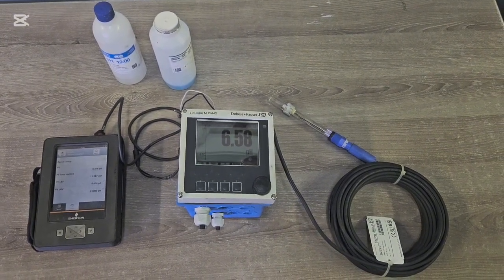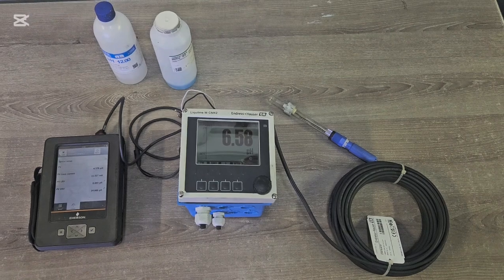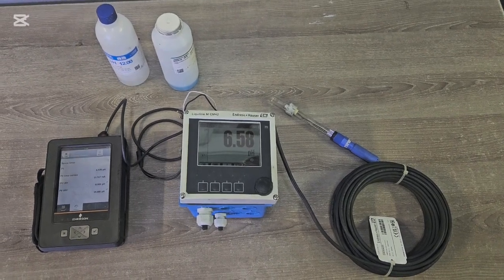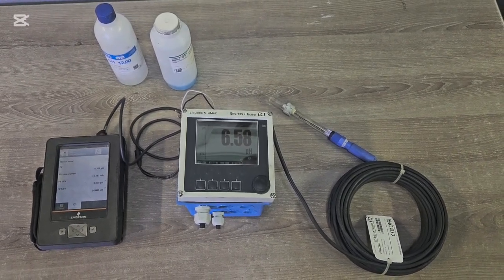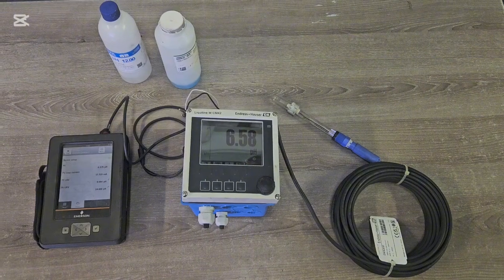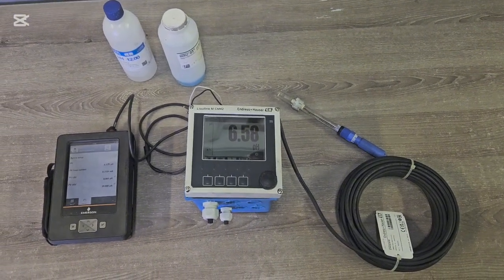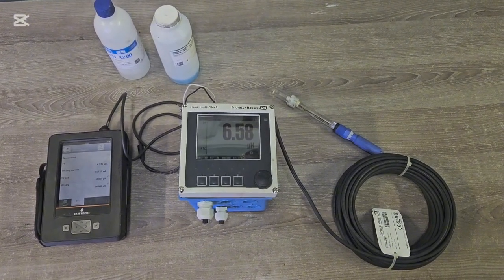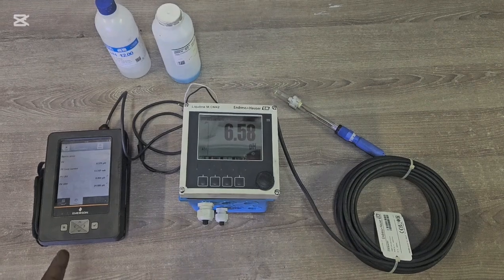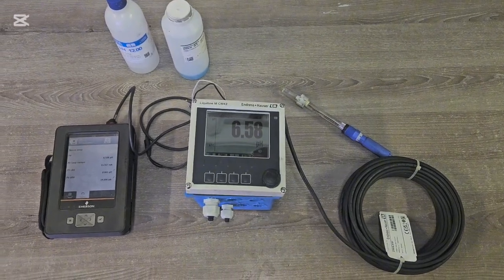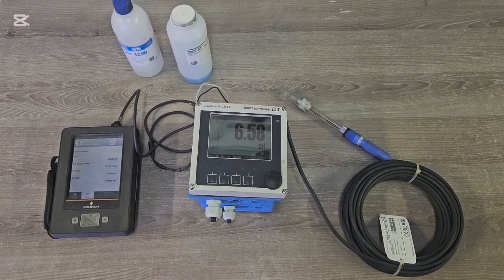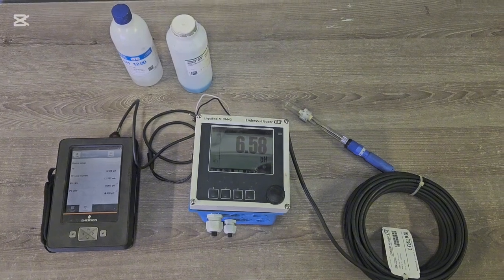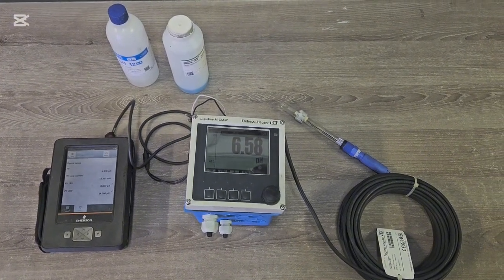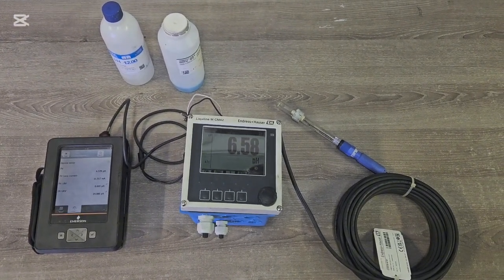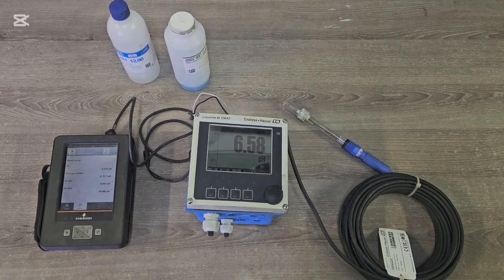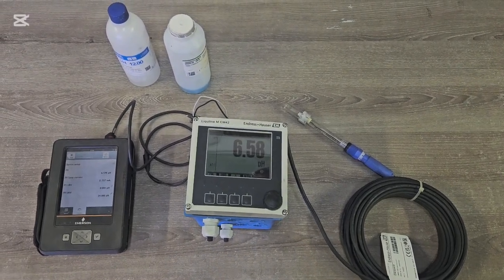But in front of me, I have connected that CM42 transmitter to a pH probe. I'm just going to introduce you to the components and their function, and give an overview of how the whole setup works. So on the left, we have an Emerson loop calibrator. In this circuit, we are using it as a current source. So we are sourcing milliamps to my transmitter from that calibrator.